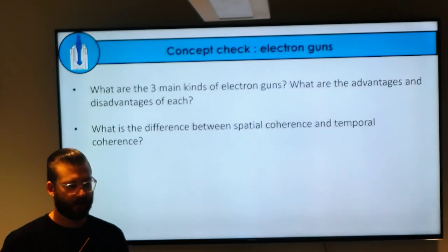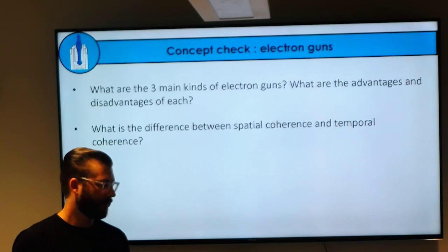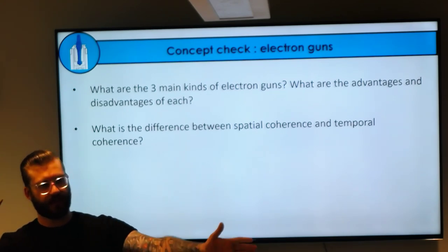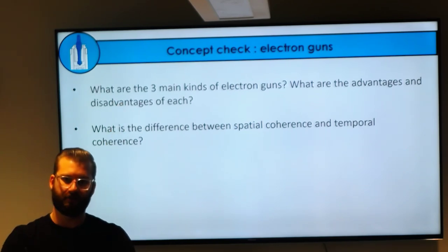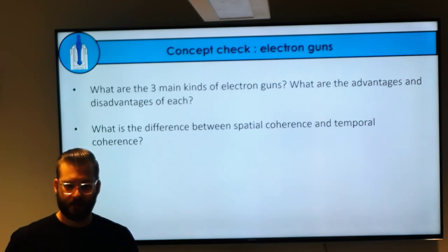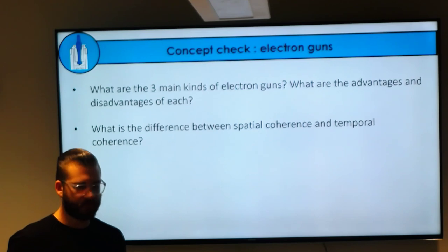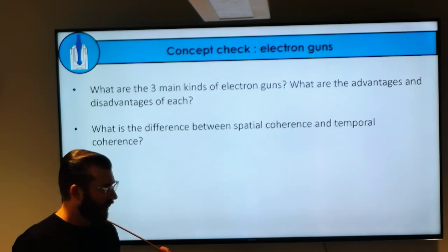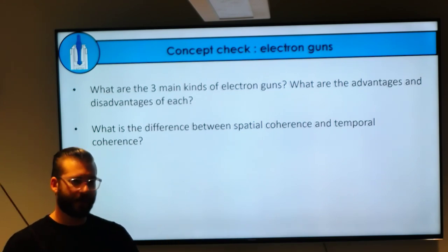What's the difference between spatial coherence and temporal coherence? Spatial coherence is the spread of the electrons—filaments give a rough spray, whereas field emission guns give a really nice parallel beam. Temporal coherence is how fast they're moving. We measure them in electron volts or kiloelectron volts: 120 keV or 300 keV microscopes. A field emission gun has an energy spread of about one to two electron volts, whereas a tungsten filament has a much wider range.